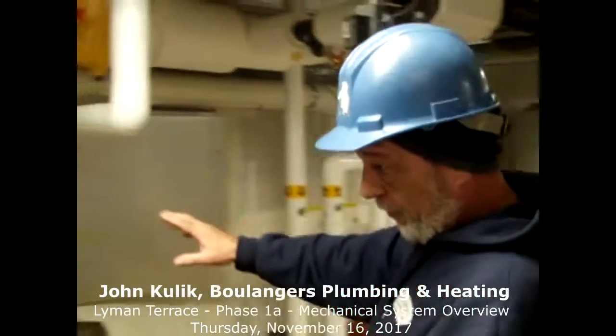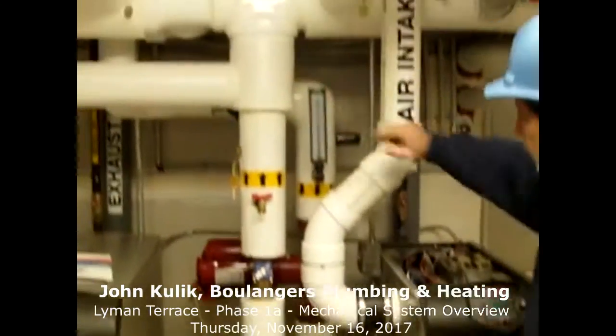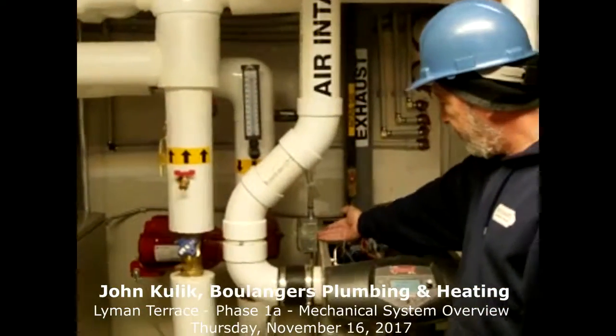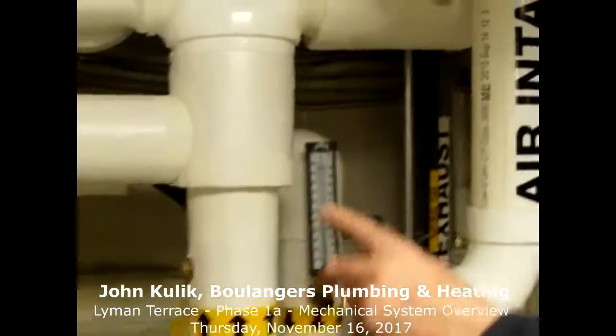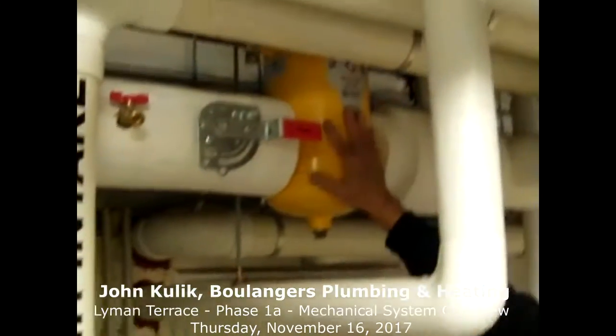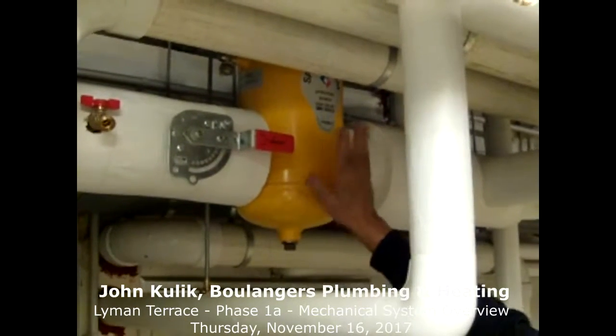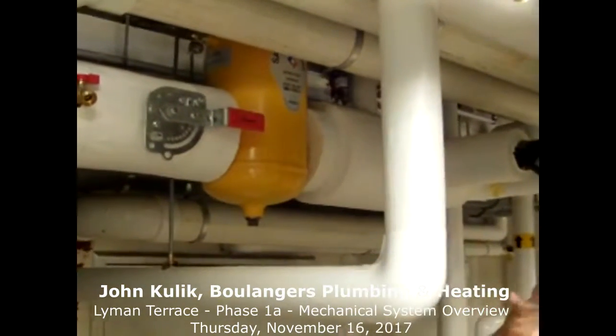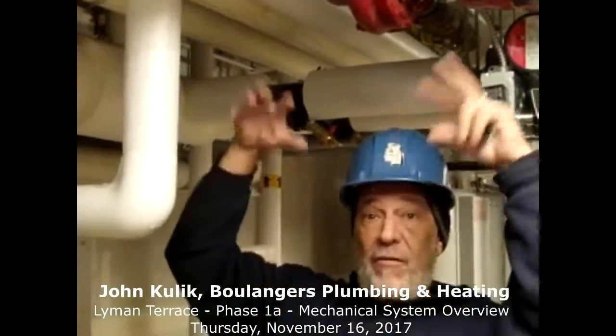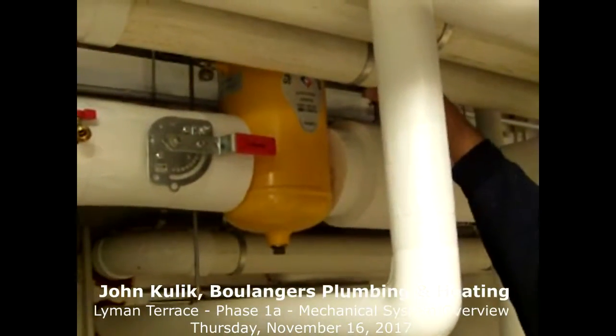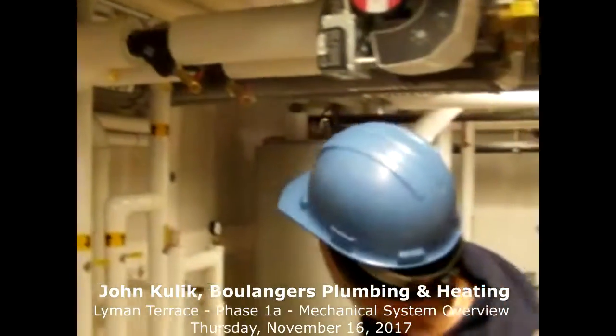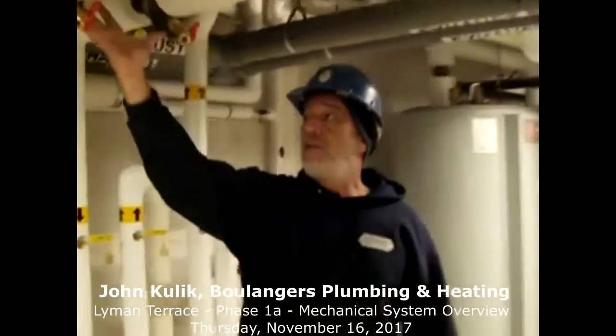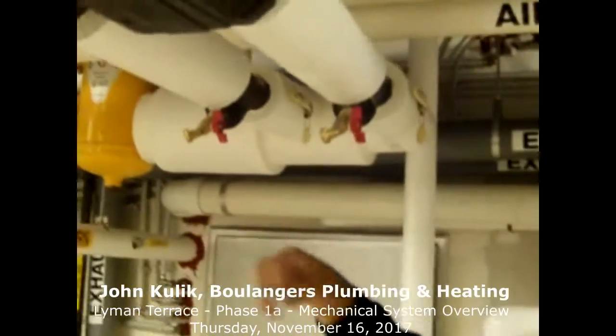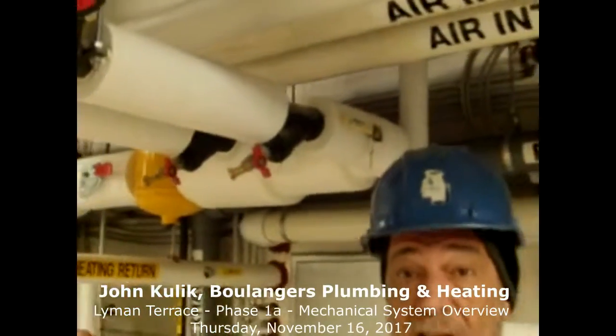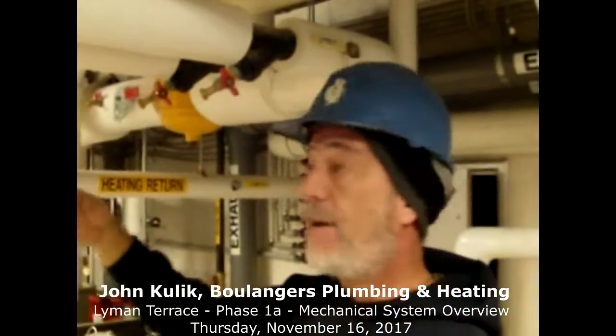And as the system runs, we have water exiting the boiler, water being drawn back in through the pumps, okay? It goes out into the main loop, goes through an air separator. So if there are any air bubbles in here, this is what removes them. There's a micro screen inside, all the little bubbles collect on it. Once they form into a bigger bubble, they rise to the top, and there's actually an exhaust port on top for the air to come out. Strainers, these protect against any larger debris, say something was to scale inside a pipe, a chip, a piece of solder, anything. It gets caught in the screen before it can go through the drive of the pumps.